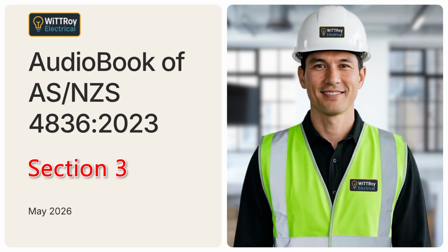3.1.8. Work on de-energized electrical equipment. 3.1.8 explains when work on de-energized electrical equipment may proceed. Work must only proceed if the electrical equipment is isolated. Any adjacent exposed conductors or conductive parts in the work area must also be controlled. They must either be de-energized and isolated or separated by barriers or distance based on a risk assessment.